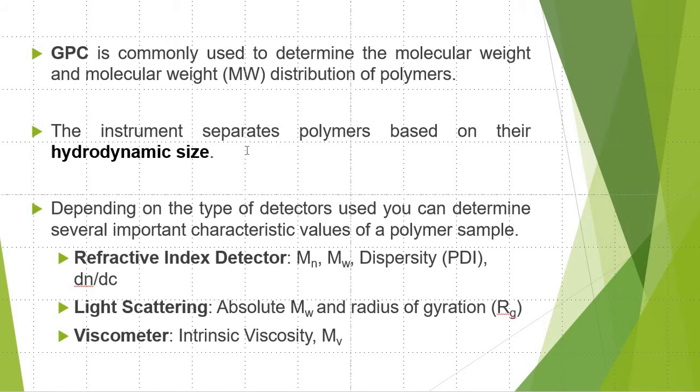Depending on the type of detectors used in a GPC system, you can determine several important characteristic values of a polymer sample. If using just a refractive index detector, you can determine the number average, weight average molecular weights, along with the dispersity or polydispersity, and also provide the refractive index increment, or dn/dc value.